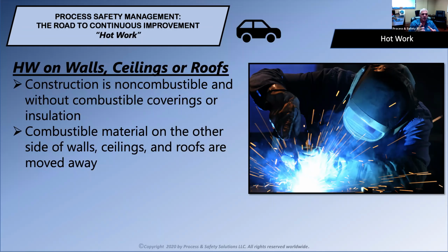and also the building itself eventually caught on fire. So making sure that you look beyond the area that you're actually doing the work, and if it's on a roof, for example, make sure that you may need a fire watch on the other side of that roof as well.